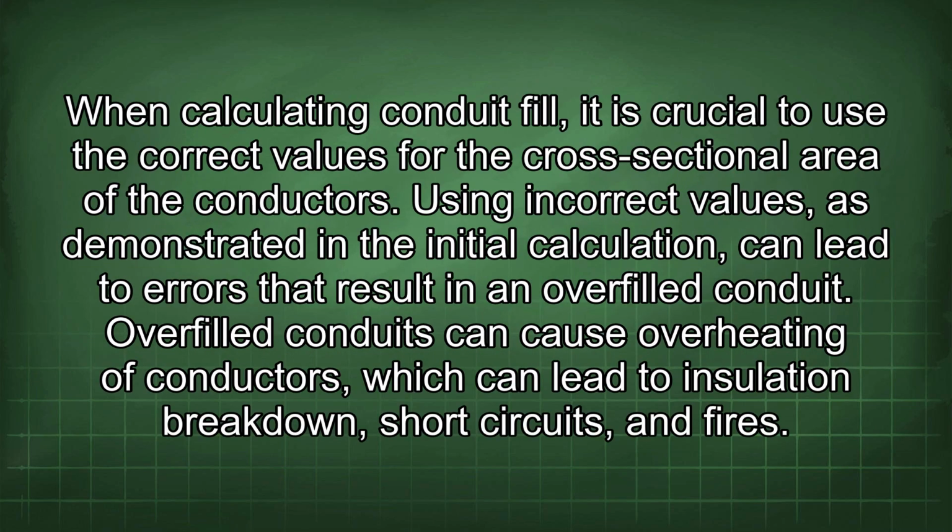When calculating conduit fill, it is crucial to use the correct values for the cross-sectional area of the conductors. Using incorrect values, as demonstrated in the initial calculation, can lead to errors that result in an overfilled conduit. Overfilled conduits can cause overheating of conductors, which can lead to insulation breakdown, short circuits, and fires.